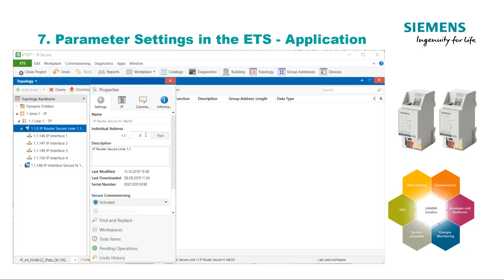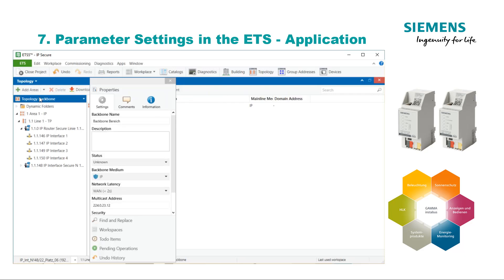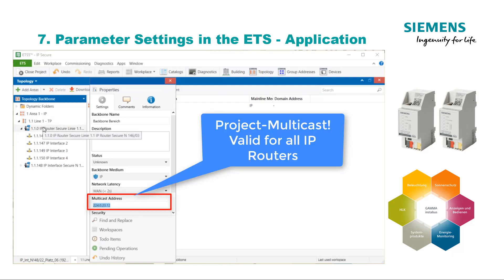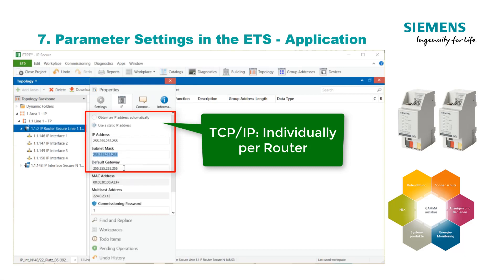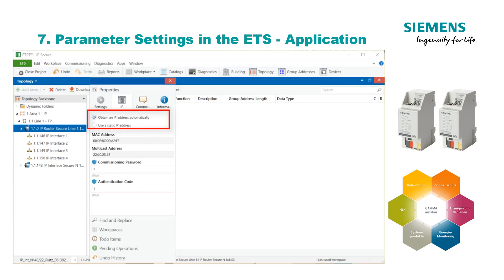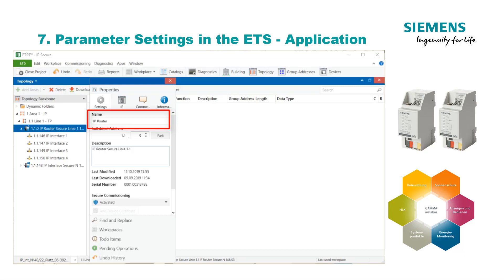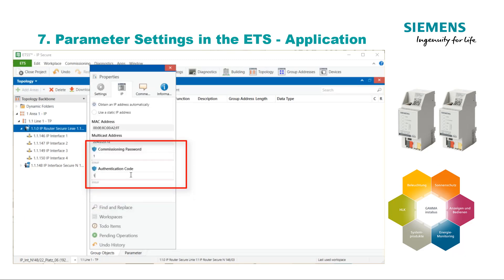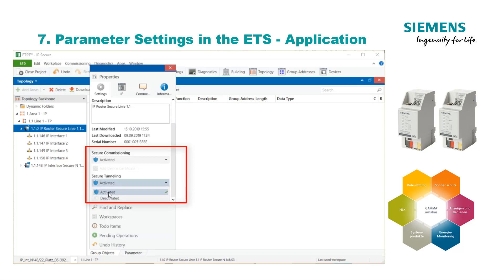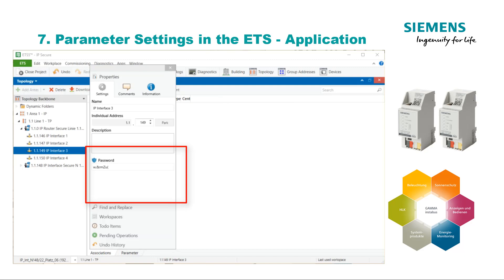Parameterization in the ETS Application. The parameterization of the Siemens KNX IP Secure devices is similar to the predecessor products. The following settings are made within the ETS standard dialog: IP network addresses, meaning multicast address and TCP/IP address; whether the IP address should be assigned manually or automatically via DHCP; assignment of the device name under which the device can be found in the ETS communication browser; and the options for secure commissioning and tunnels, including whether they should be active and which passwords are set for them.